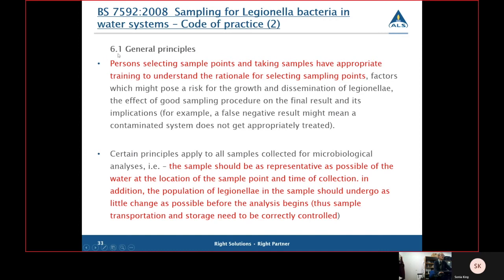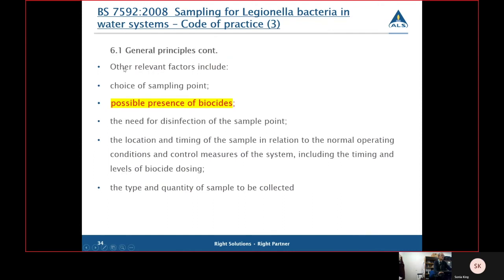This is basically what this covers. Carrying on here. But the thing you've got to watch is you must neutralize all biocides. Now, if there's organic biocides in there, they are difficult, or in some of them impossible to neutralize. But if you've got chlorine, chlorine dioxide, or copper silver, there are competent ways of doing this. But this is absolutely crucial.